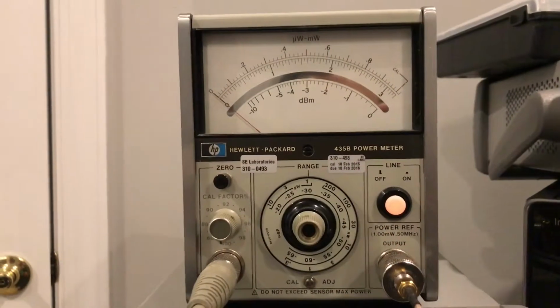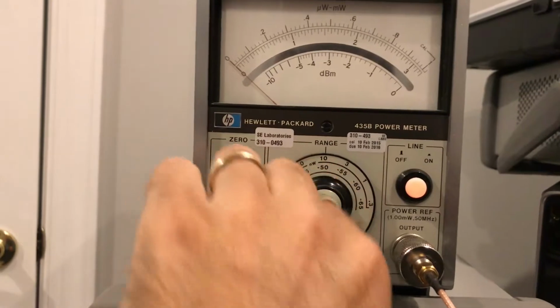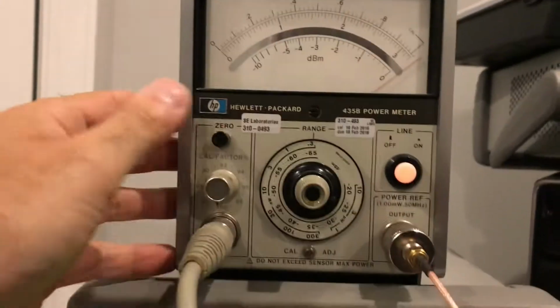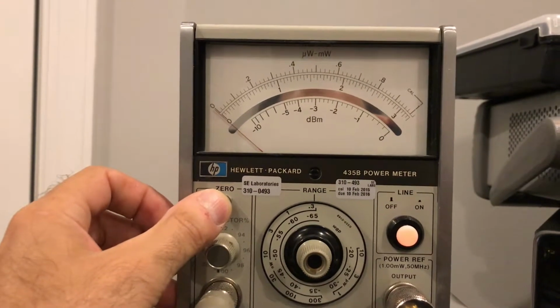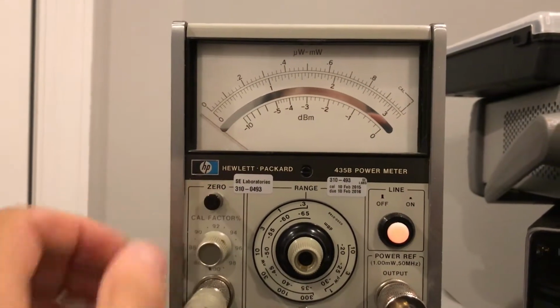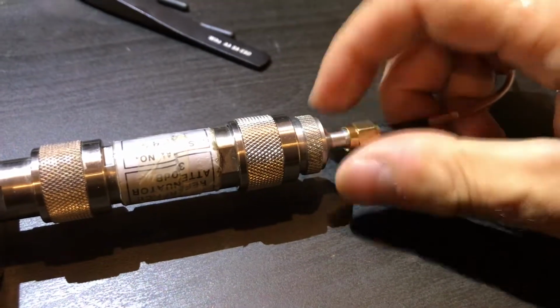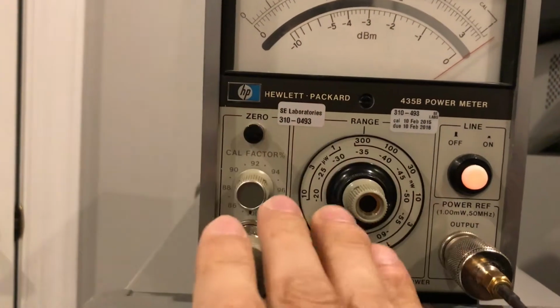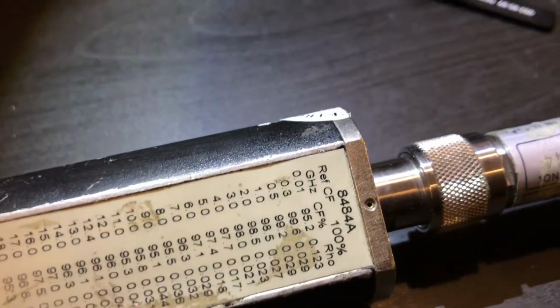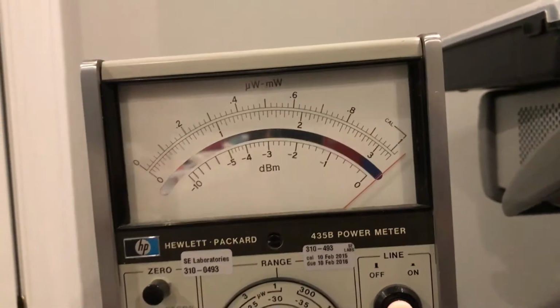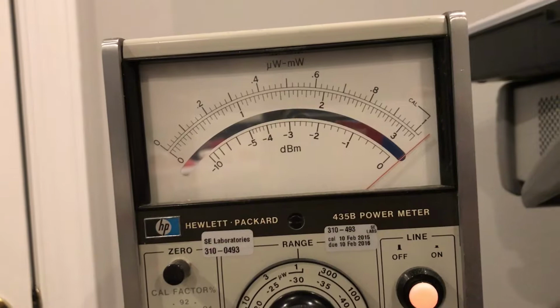So, all right, and just real quick for the other sensor, go ahead and zero it as well. So that's zeroed, and we'll go ahead and hook up our reference signal. All right, and bring that up. All right, and this one is a reference cal of 100%. So we've got our knob set to 100% now, and we'll bring that cal adjust.